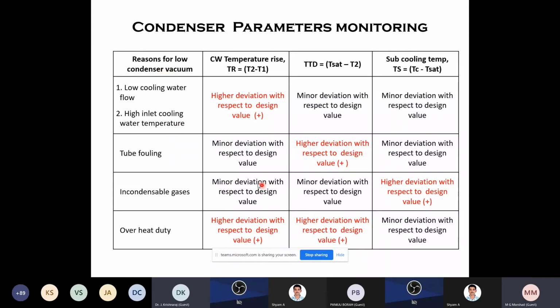Likewise, when there is tube fouling, the deviation of the TTD will be very high, and the other two will have very minimum deviation. So you can say that it is tube fouling. Suppose there are incondensable gases. In such cases the subcooling temperature deviation will be higher, and the other two will be very minor. And if there is overduty, meaning excess, the higher deviation is in both, and there will be a minor deviation in the other.